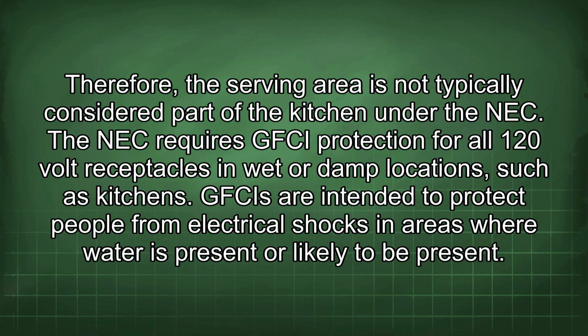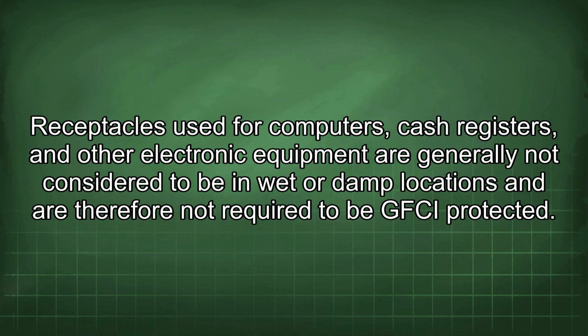The NEC requires GFCI protection for all 120-volt receptacles in wet or damp locations, such as kitchens. GFCIs are intended to protect people from electrical shocks in areas where water is present or likely to be present. Receptacles used for computers, cash registers, and other electronic equipment are generally not considered to be in wet or damp locations and are therefore not required to be GFCI protected.